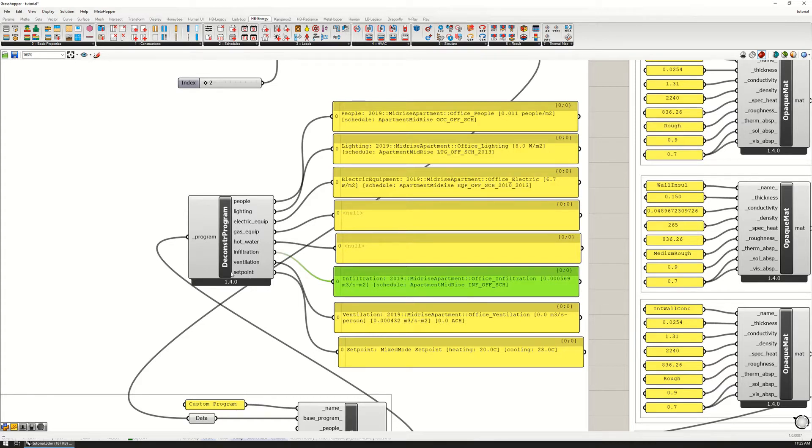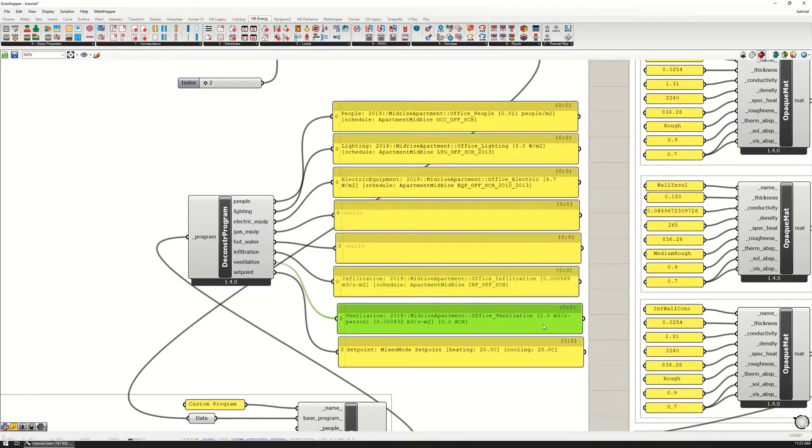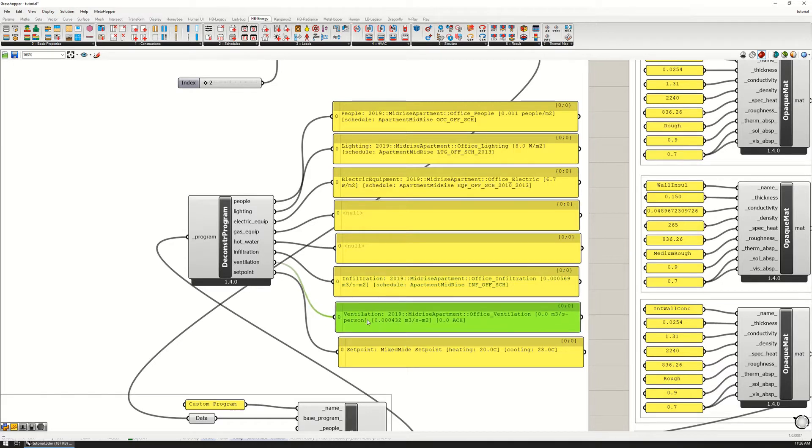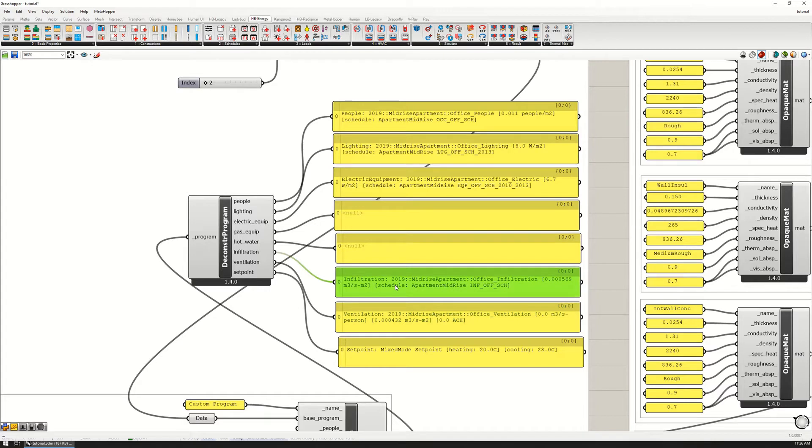The ventilation is set to 0.0004 cubic meters per second per square meter. This is for fresh air, and the infiltration is the uncontrolled air that is coming in and out of the envelope.